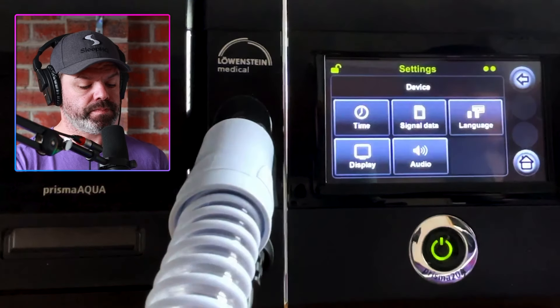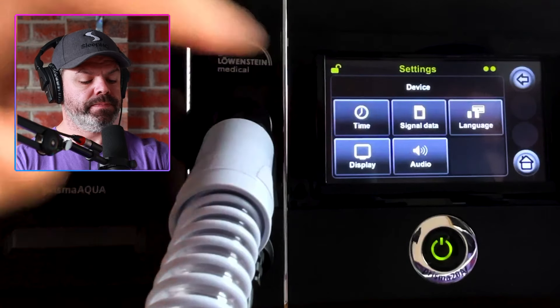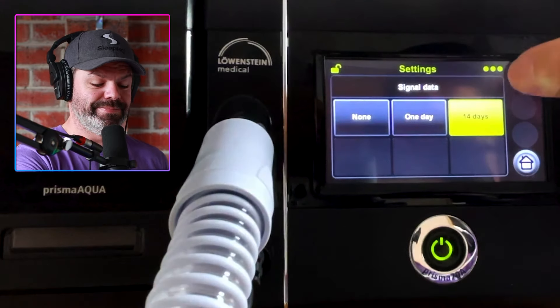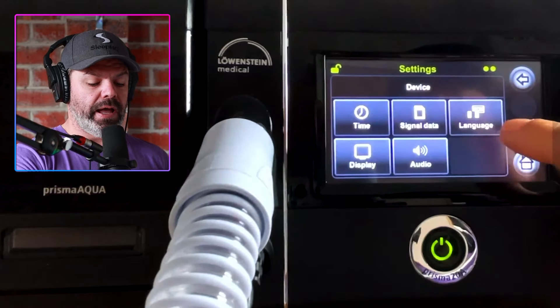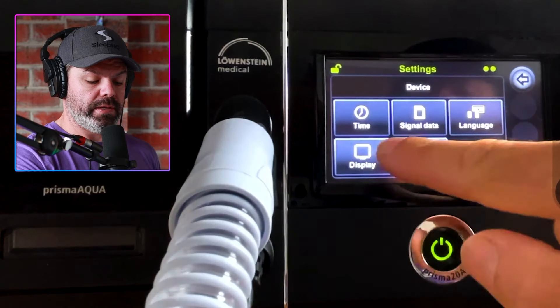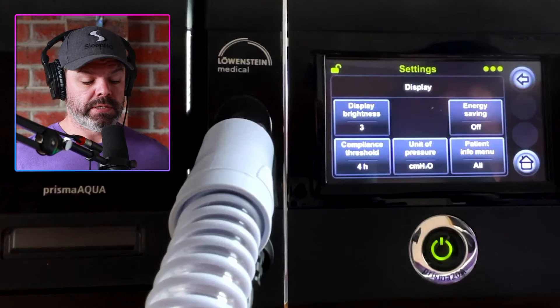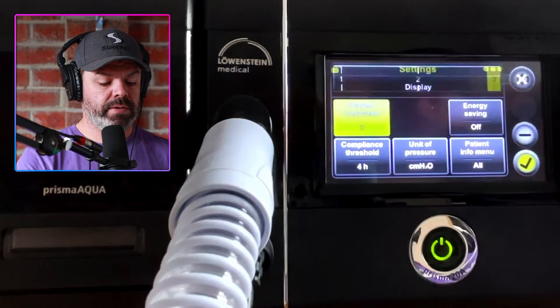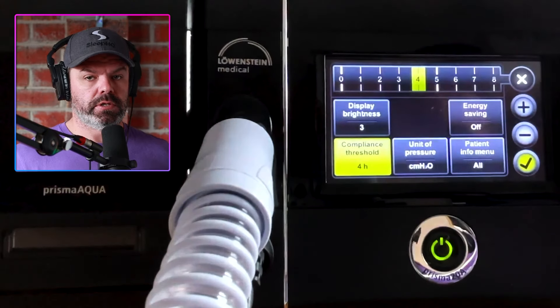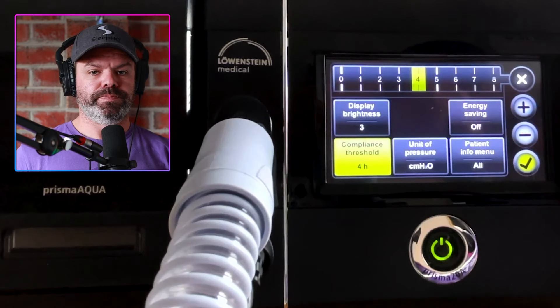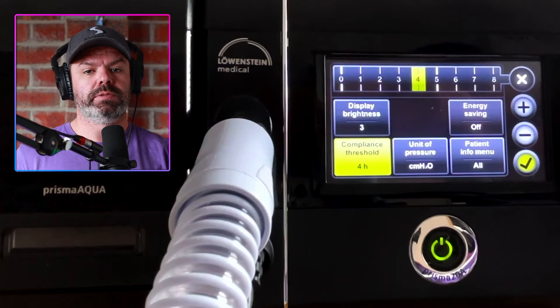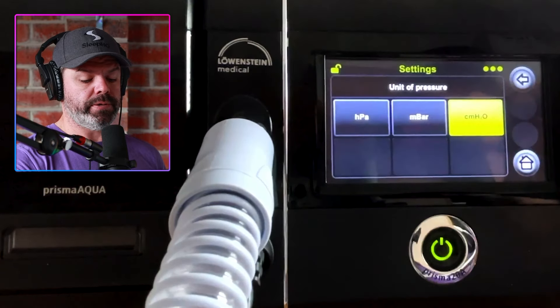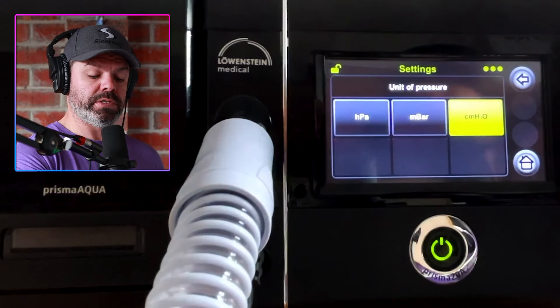Under device settings we can set time, date, and time zone. Display lets us change brightness between one, two, and three. We can change the compliance threshold — most companies use four hours per night to be deemed compliant with therapy, but you can change that. We can also change the unit of pressure: HPA, mbar, or centimeters H2O — most people use centimeters H2O. The patient info menu should be set to 'all' to give you all the statistics in the information section.